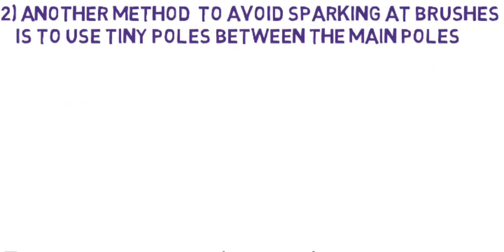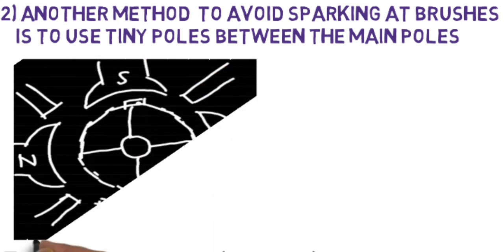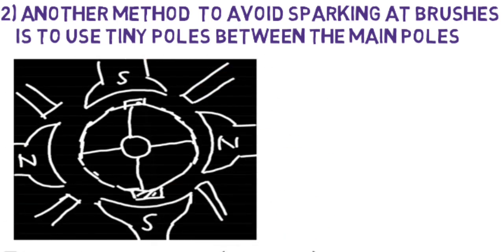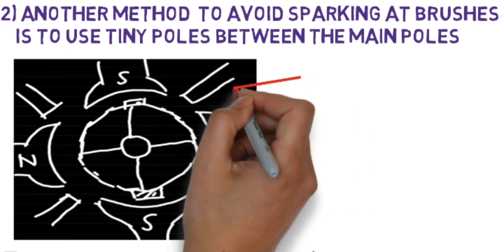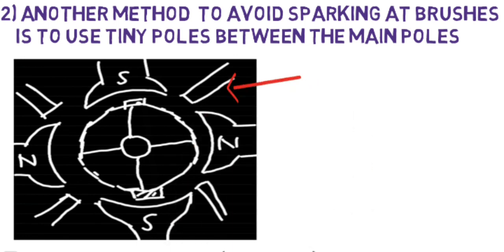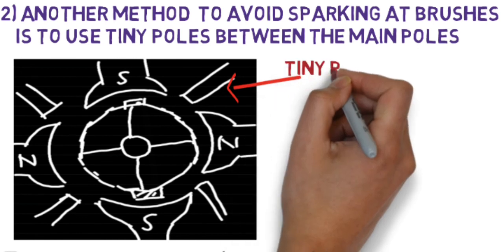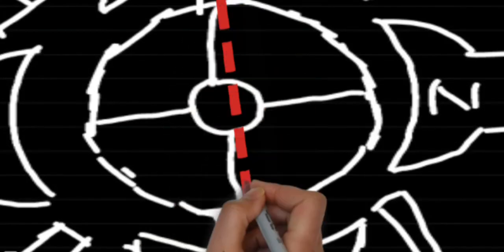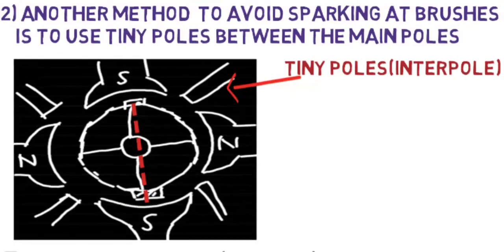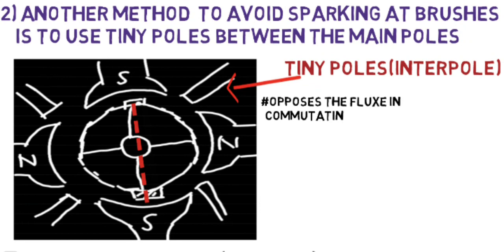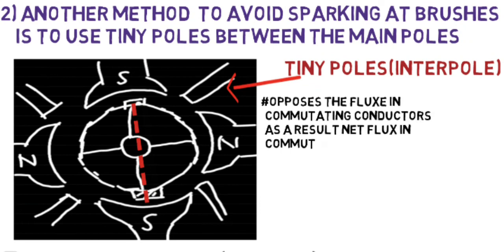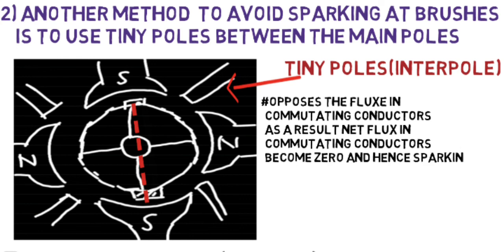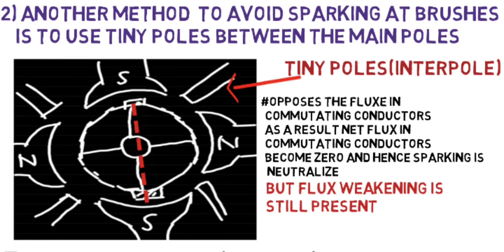The second remedy is to use interpoles — small poles placed between the main poles. Interpoles are used to avoid sparking in commutation. Sparking occurs due to flux present in commutating conductors at the MNA. These interpoles oppose the flux in the commutating wires, making the net flux in commutating conductors zero, thus neutralizing sparking. However, flux weakening is still present with this method.